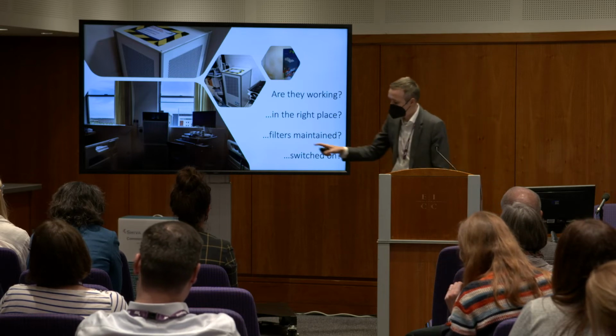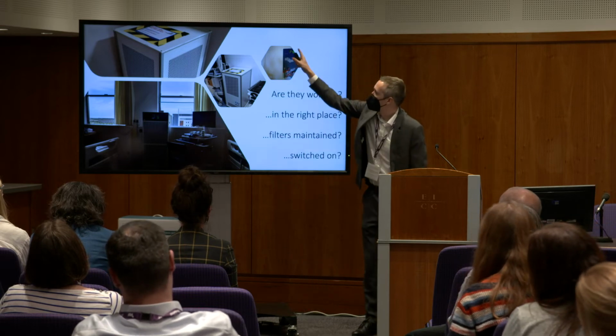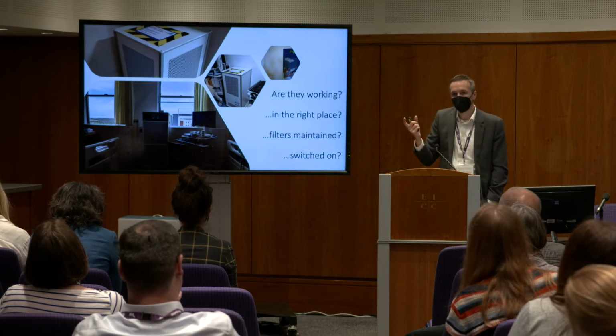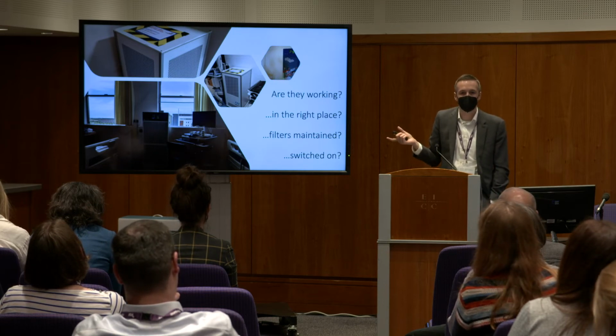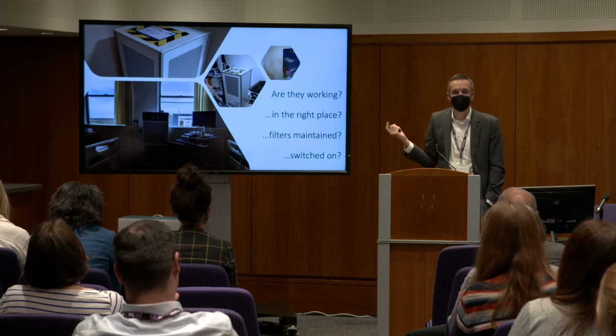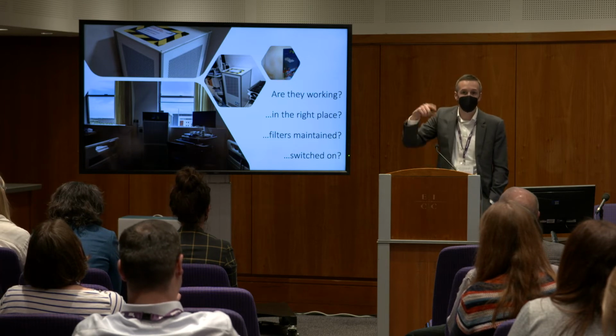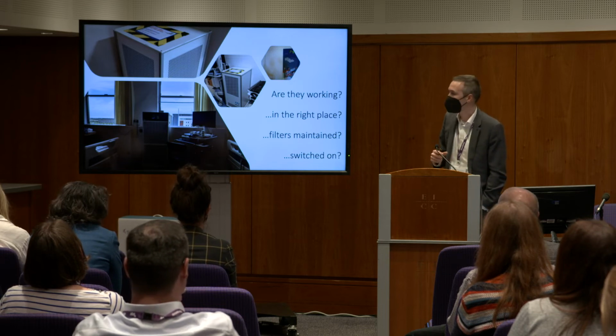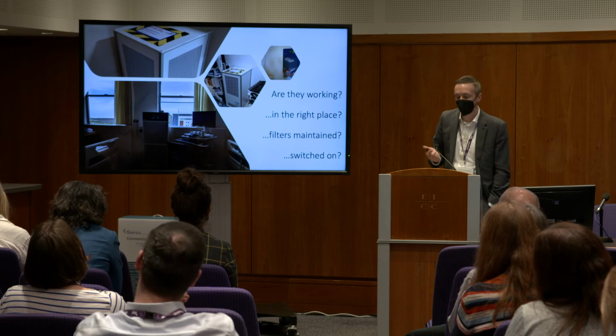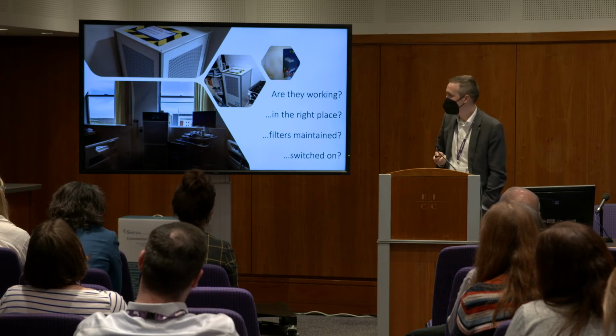One of the key things we found is that on the top they've got these little boxes. You can't see that one because I cut it off. But they're actually just Wi-Fi boxes, so you don't have to send a person to check whether the filter's healthy, or whether it's on. The machine will tell you whether it's on. It will tell you whether someone's fiddled with it and put it up to clean room setting or whatever, and you can remotely just turn it down. So you're stopping people having to go and see these units unless you need to. It will tell you if the bulbs have blown or something like that. And 9 times out of 10 they're not switched on anyway.